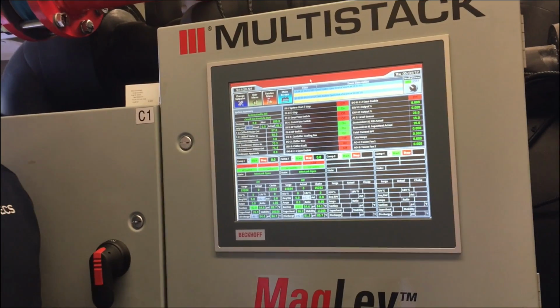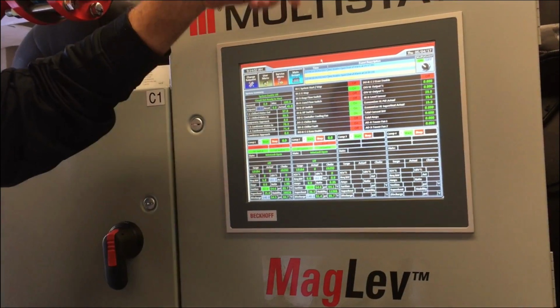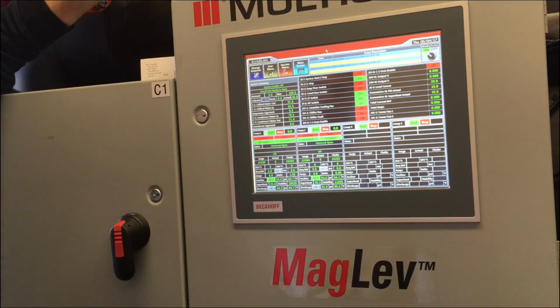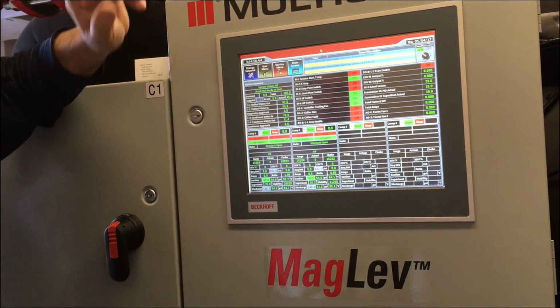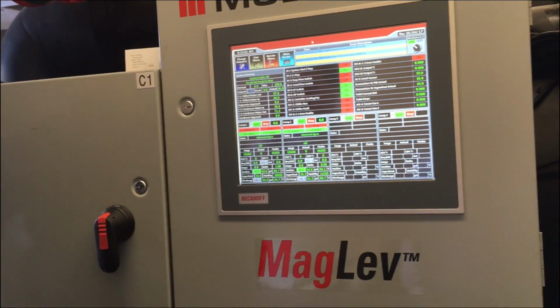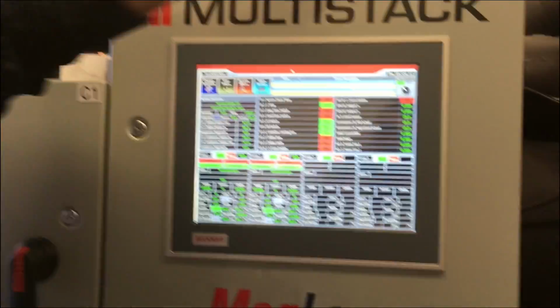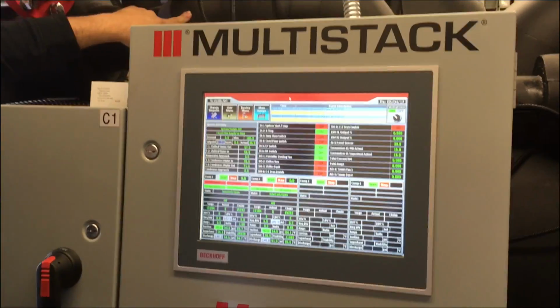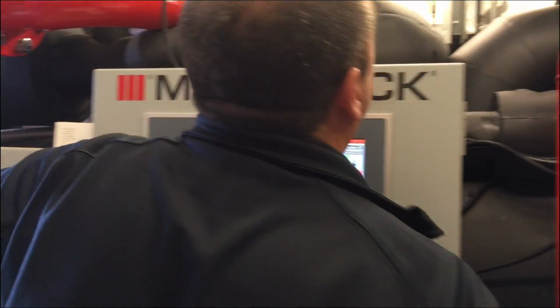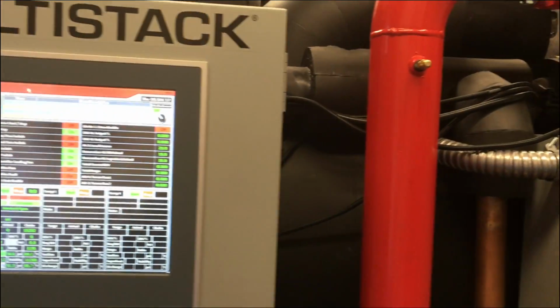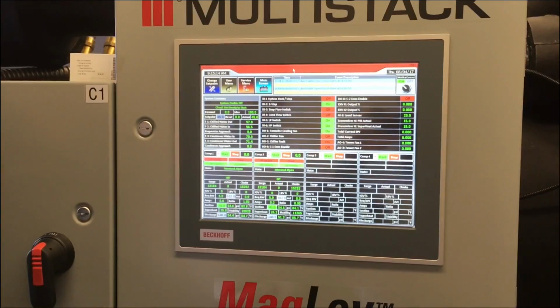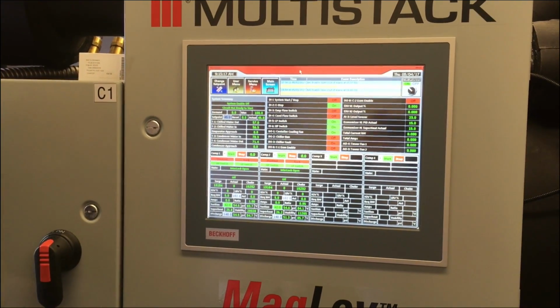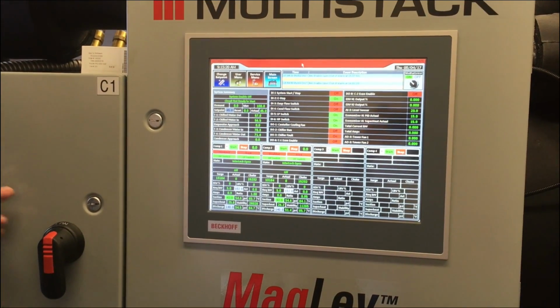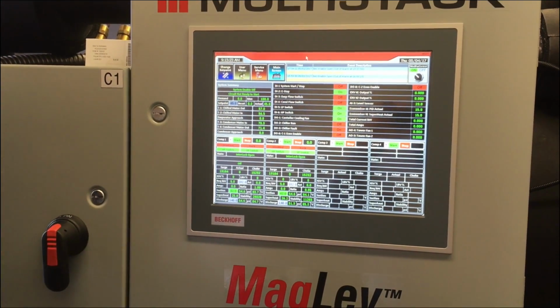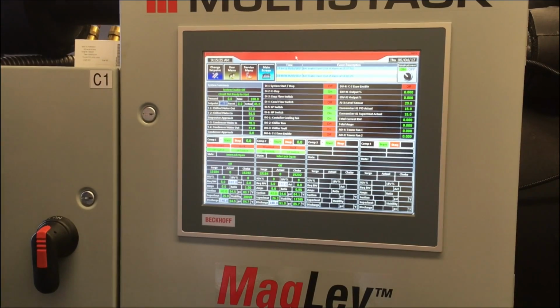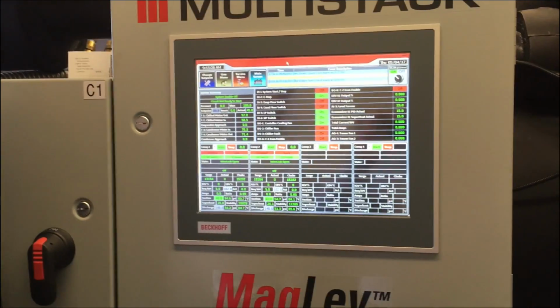Both compressors are completely isolatable, so you could work on that one while this one runs, so you shouldn't have to have downtime just because you have a compressor issue. They're shut off on all sides. The discharge has one, the suction has one, the economizer, which we'll talk about, has one. Right here is a ball valve, right here. And the liquid cooling line, which is on the back side, which we'll get to when we turn it on, also has isolation. So you could isolate this compressor. You could take it down and put a new one in if you had to. Hopefully we won't. Or you could work on any piece of it and keep the chiller running. So you've got good redundancy right there with having two compressors, and one can be serviced while the other runs.